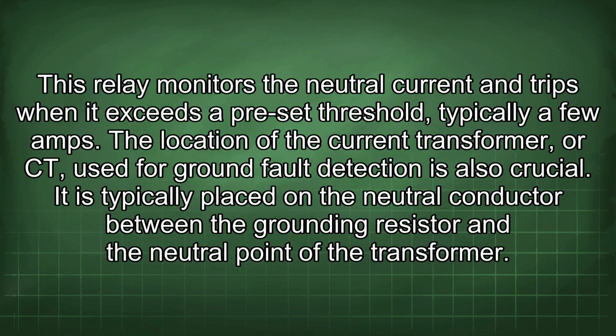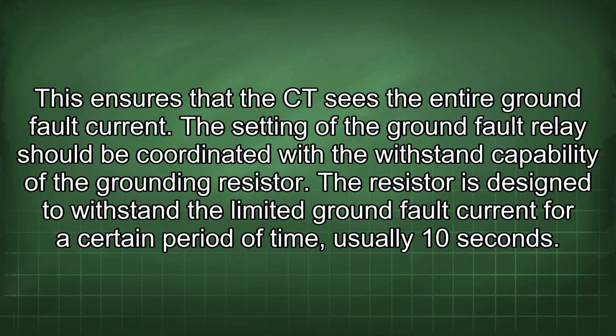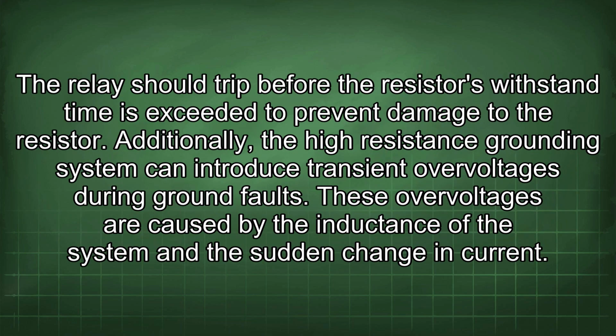The location of the current transformer, or CT, used for ground fault detection is also crucial. It is typically placed on the neutral conductor between the grounding resistor and the neutral point of the transformer. This ensures that the CT sees the entire ground fault current. The setting of the ground fault relay should be coordinated with the withstand capability of the grounding resistor. The resistor is designed to withstand the limited ground fault current for a certain period of time, usually 10 seconds. The relay should trip before the resistor's withstand time is exceeded to prevent damage to the resistor.